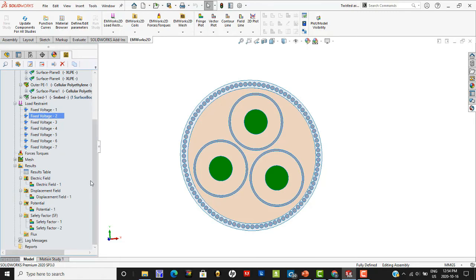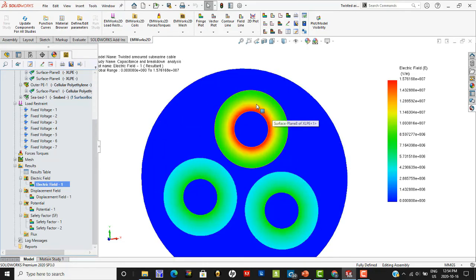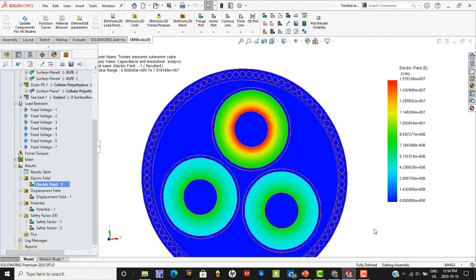What kind of results can I expect from EMS? I can plot the electric field, and the value achieved is around 15 million volts per meter. The breakdown voltage of the XLPE we chose was close to 21 million volts per meter. So at a maximum operating voltage of around 190 kV, this particular cable design behaves perfectly fine and there is no breakdown.